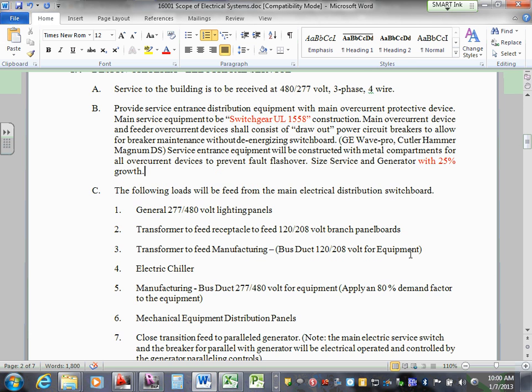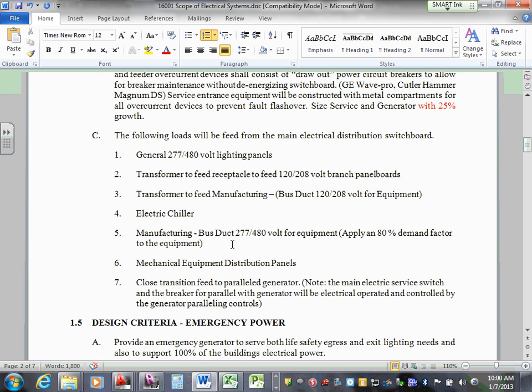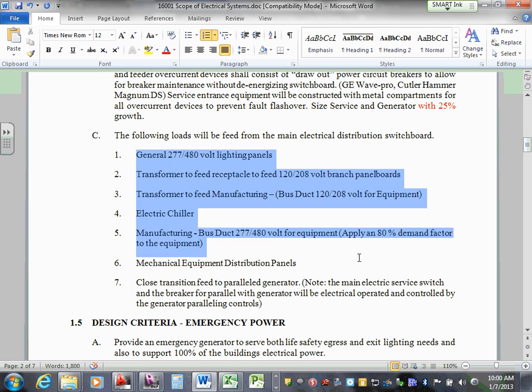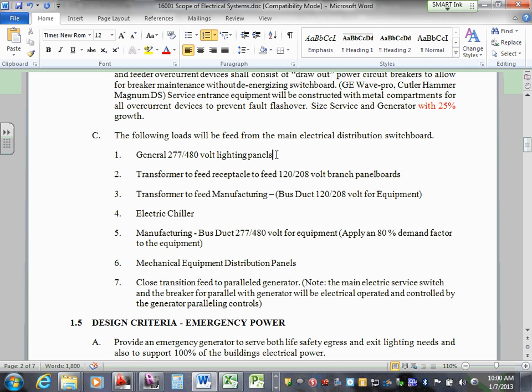In item C, we talked about how some of the loads would be fed. We're talking about 277 volt for lighting, so they come out of the 277/480 volt lighting panels. We're talking about transformers to feed 120/208 volt for any of our 120/208 volt needs. Transformers to feed manufacturing. In the manufacturing area, we've got some heavier loads at 120 or 208.